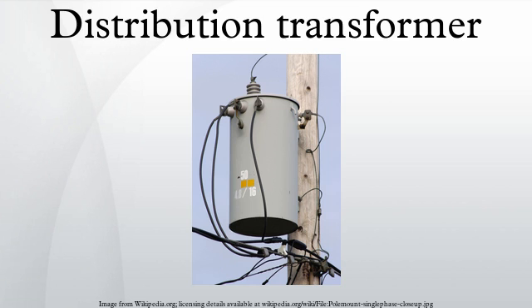In European countries using its system, the secondary is often the three-phase 400Y/230 system. There are three 230V secondary windings, each receiving power from a primary winding attached to one of the primary phases. One end of each secondary winding is connected to a neutral wire, which is grounded. The other end of the three secondary windings, along with the neutral, are brought down the service drop to the service panel. 230V loads are connected between any of the three-phase wires and the neutral.